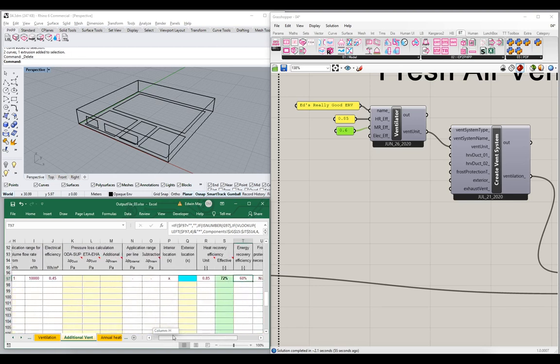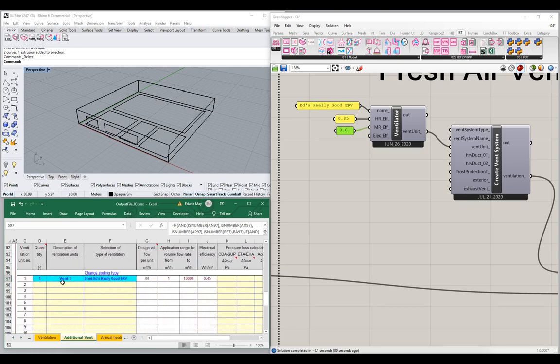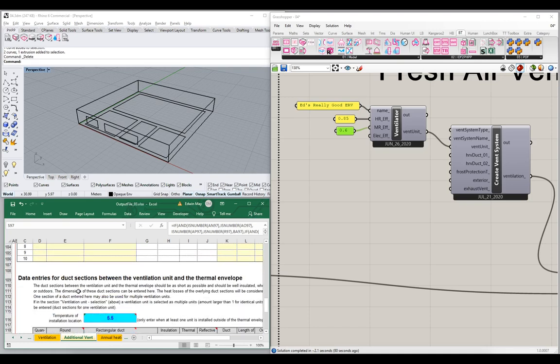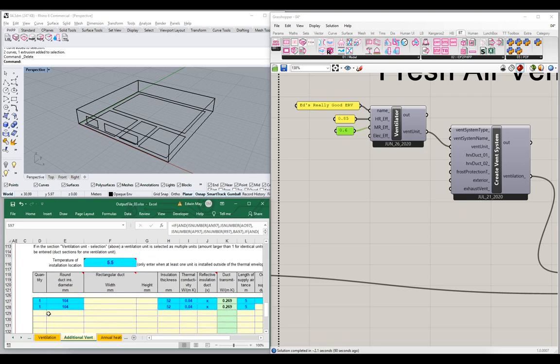Let's take a look at our overall system efficiency. We have this 85% efficient unit, but notice we've only got a 72% system efficiency. Why is that? Well, the system efficiency takes into account both the unit and the ducting. So we need to configure the ducting properly in order to boost that system efficiency back up to where it ought to be — above 75% at least. Let's come down to where we enter the ducts. The relevant data points are the size, level of insulation, type of insulation, and the length — the length being probably the most important.